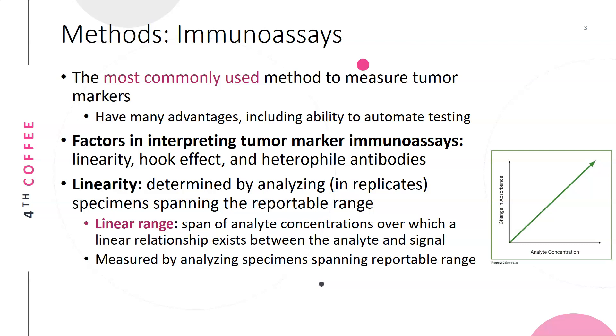Linearity is determined by analyzing replicates of specimens spanning the reportable range — from very low to very high levels. The linear range is the span of analyte concentration over which there is a linear relationship between the analyte and the signal. For example, if the signal is absorbance, the higher the analyte concentration, the higher the absorbance and the higher the signal.